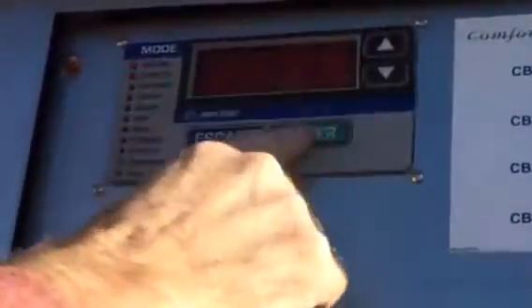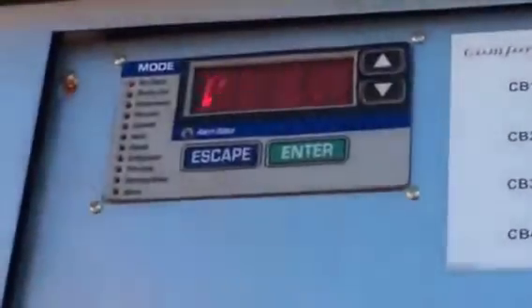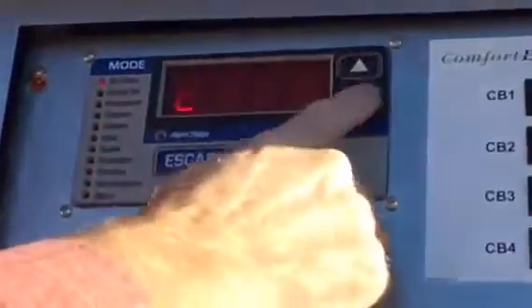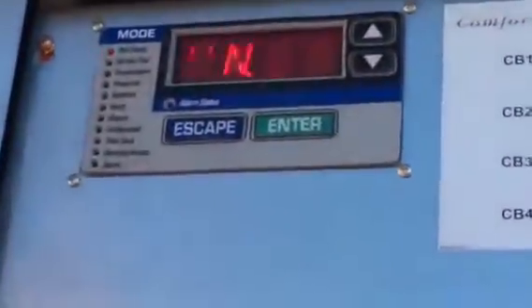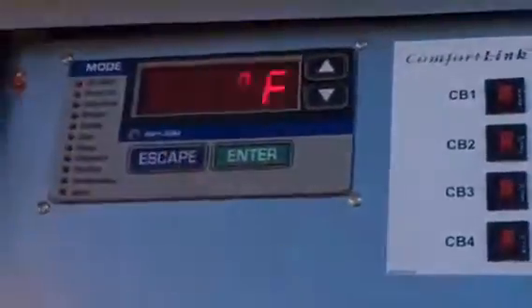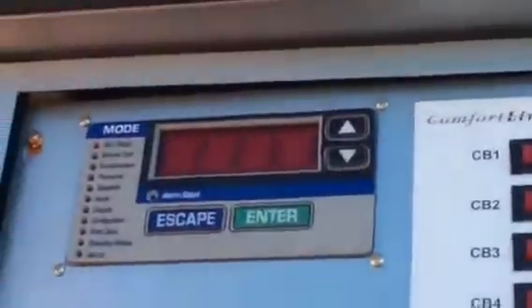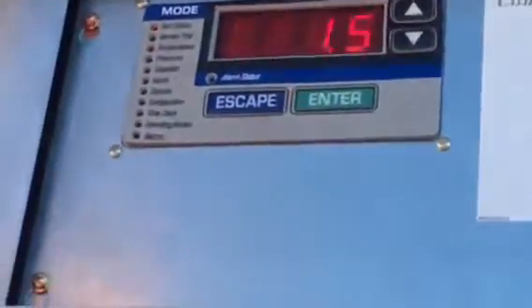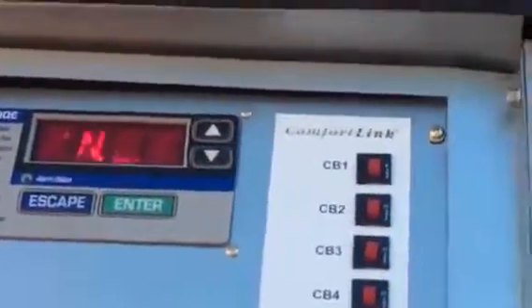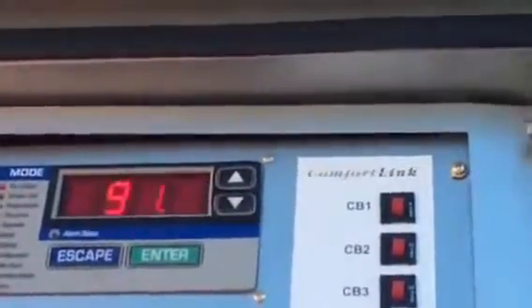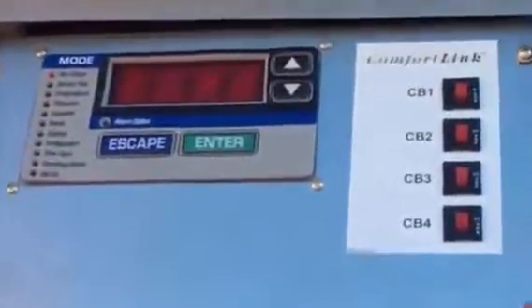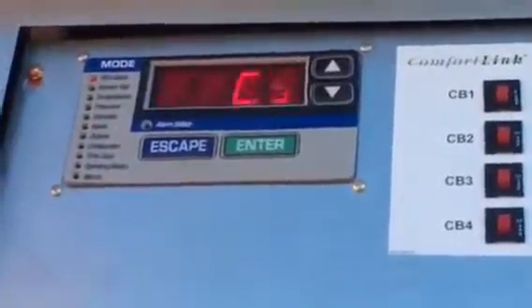Screen goes blank, and now I can go to any other set point. There's, choose run status. Here's another one where I have view, economizer, cooling, trips. In the book, it'll explain what these different explanations are for trip points, but that's where I'm going to go after I've read the book. If I expect something to happen and it's not, these trip points will give me a clue about when a compressor stage might happen.